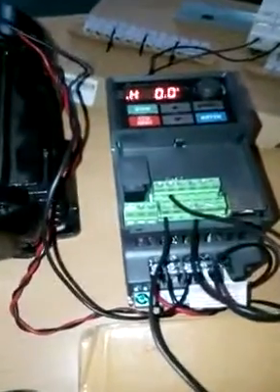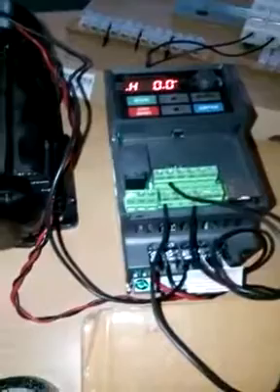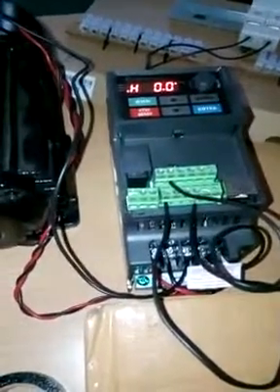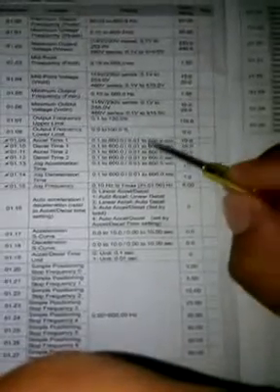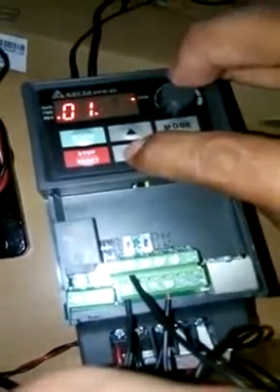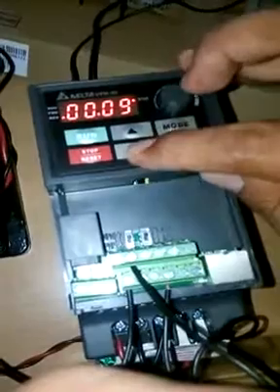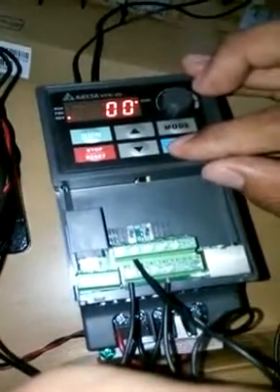If you want to start and stop the motor on the spot or with a specific time delay, you can do that through this parameter. The parameter is acceleration time 1. The default setting is 10 seconds, and you can set it up to 600 seconds.